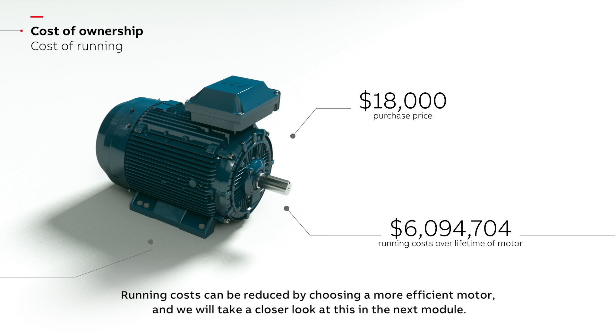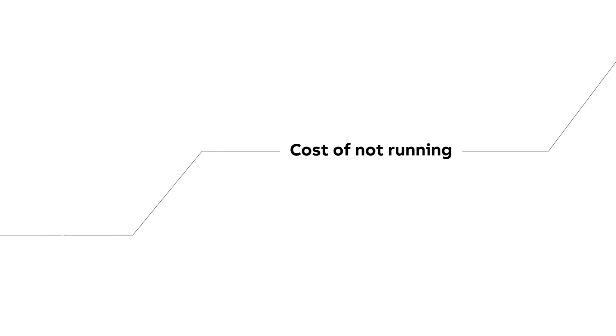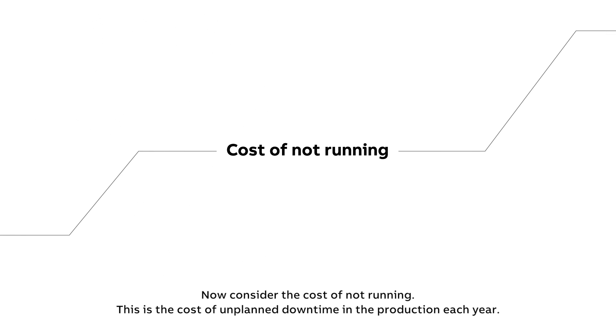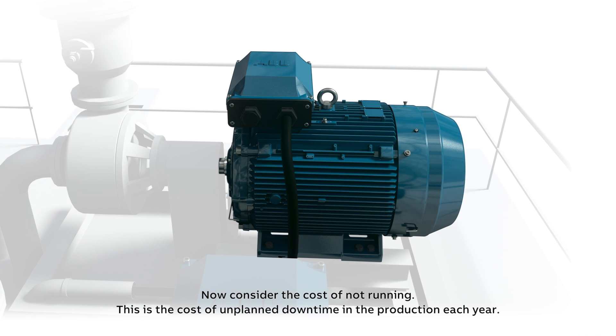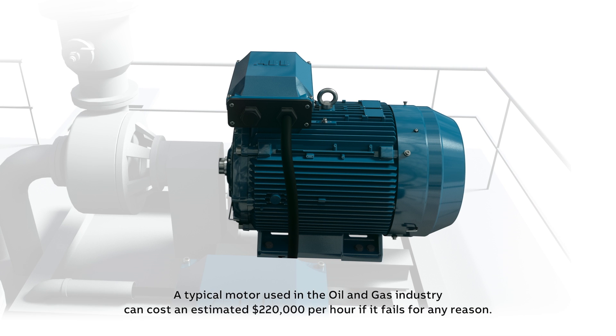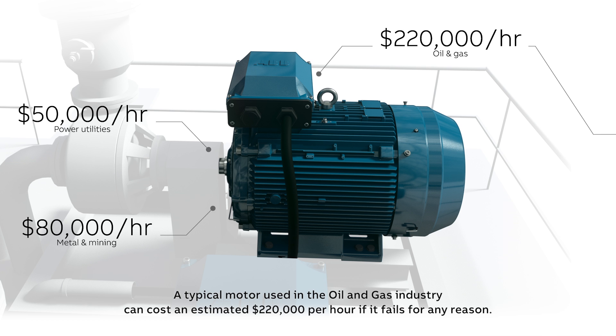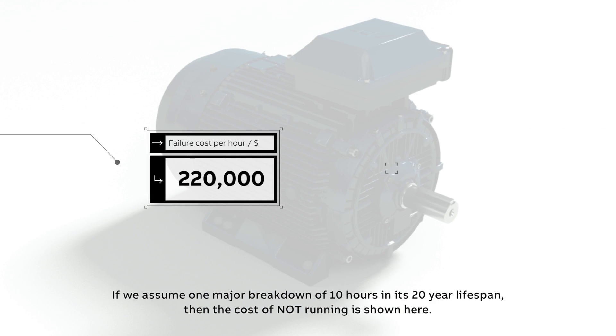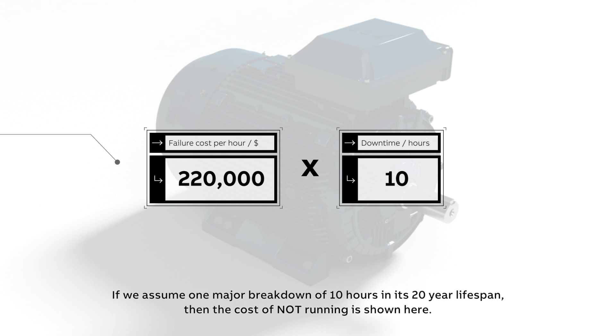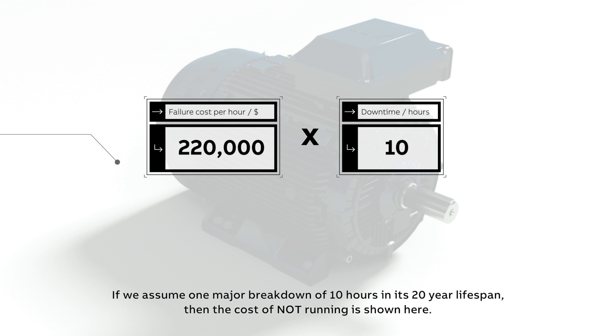Running costs can be reduced by choosing a more efficient motor, and we will take a closer look at this in the next module. Now consider the cost of not running — this is the cost of unplanned downtime in the production each year. A typical motor used in the oil and gas industry can cost an estimated $220,000 per hour if it fails for any reason. If we assume one major breakdown of 10 hours in its 20-year lifespan, then the cost of not running is shown here.